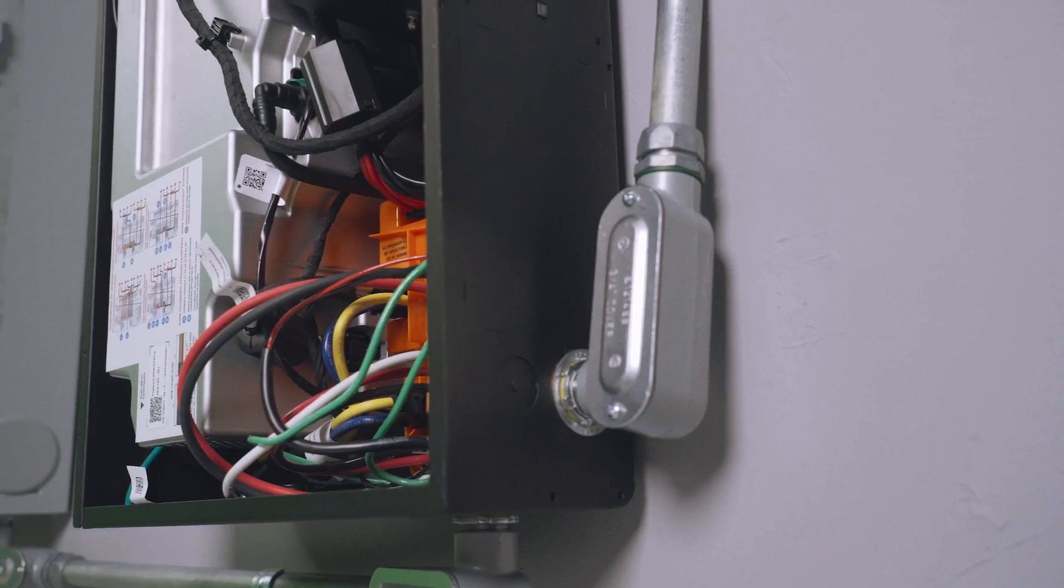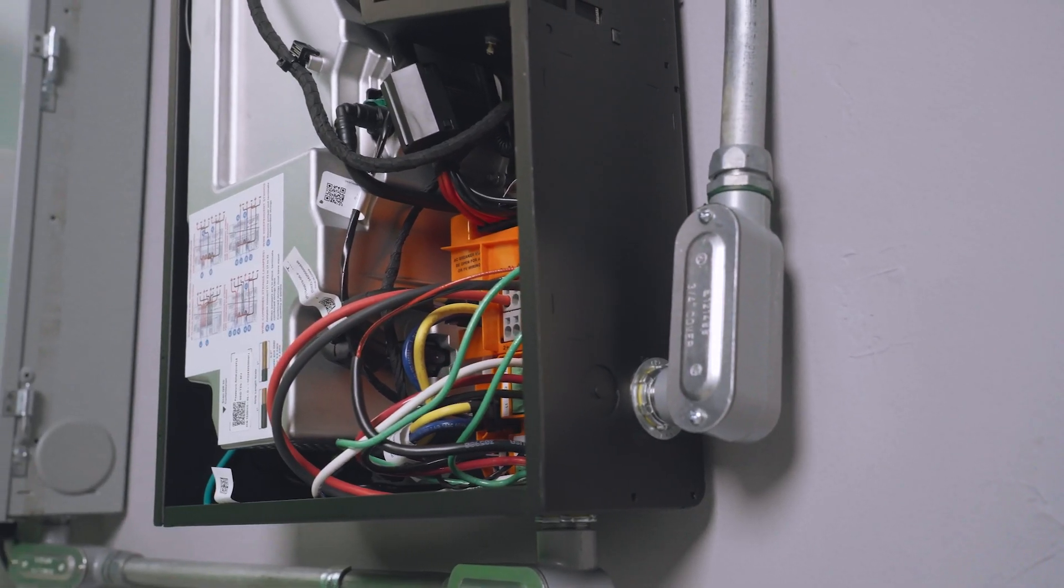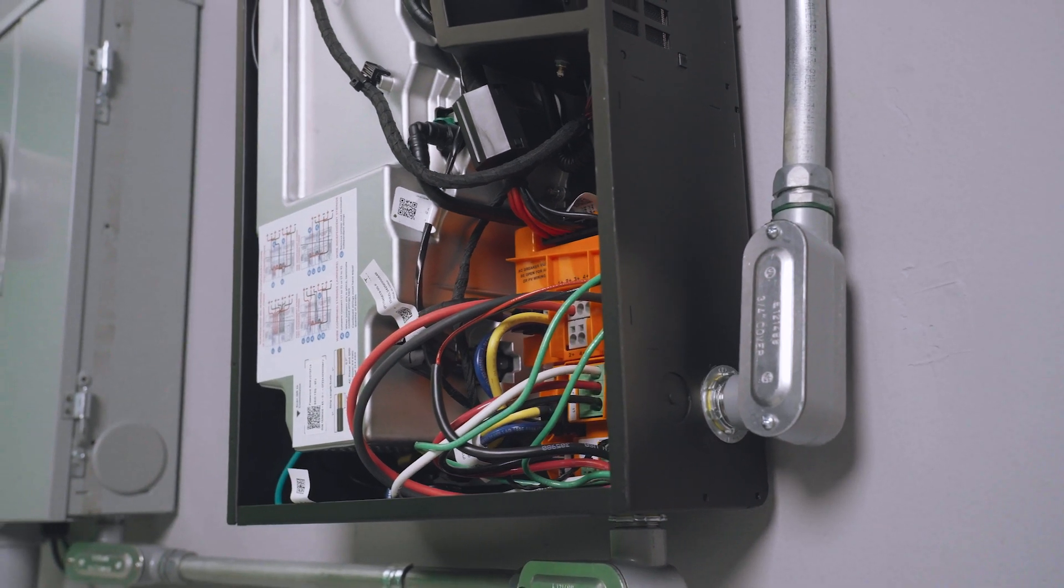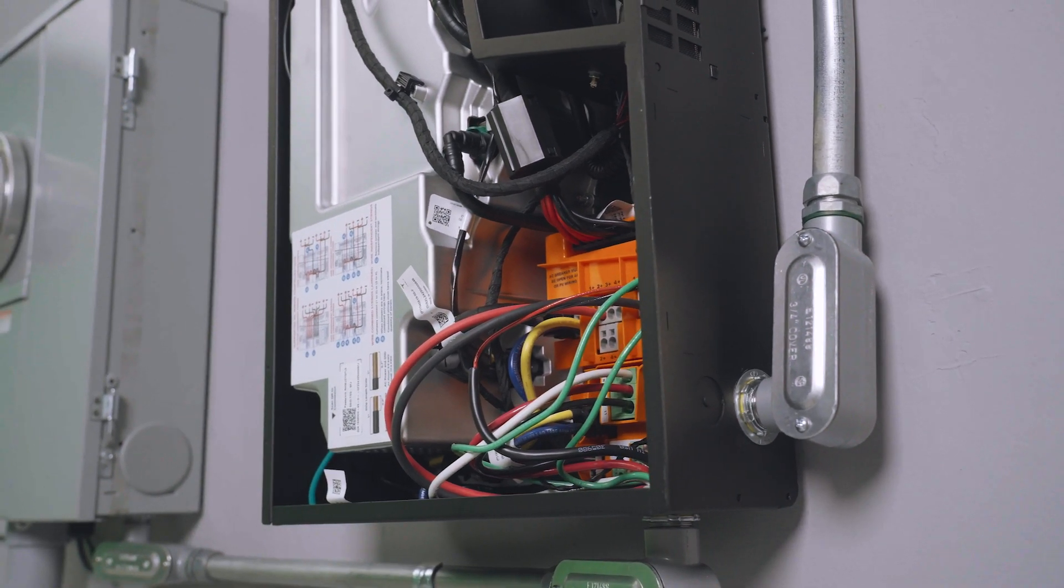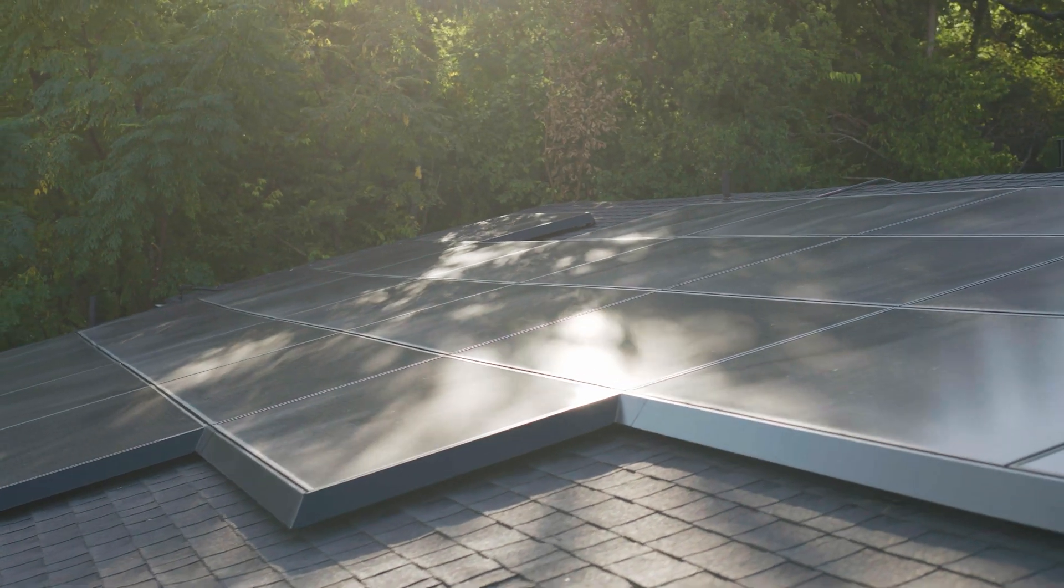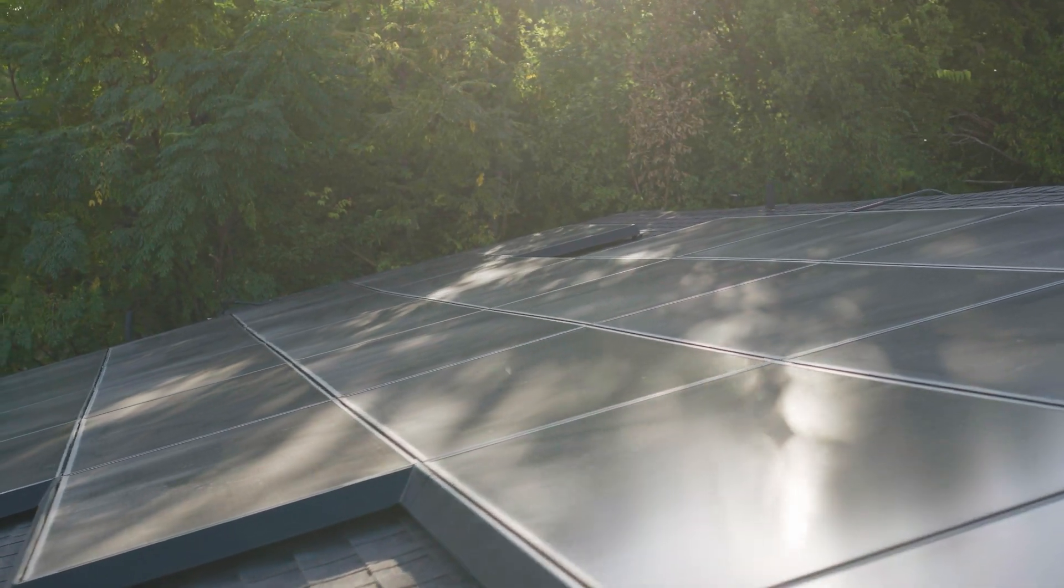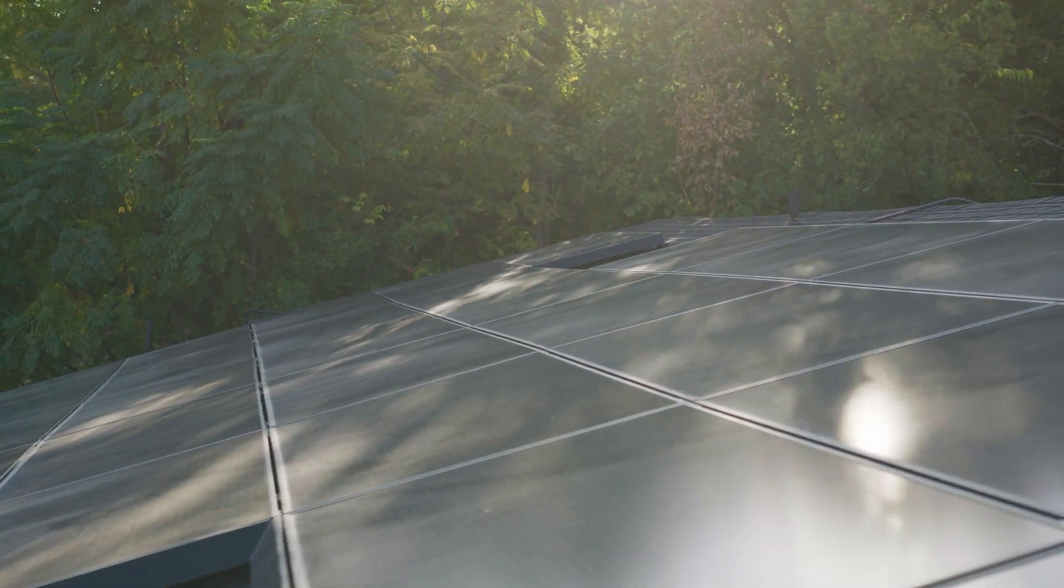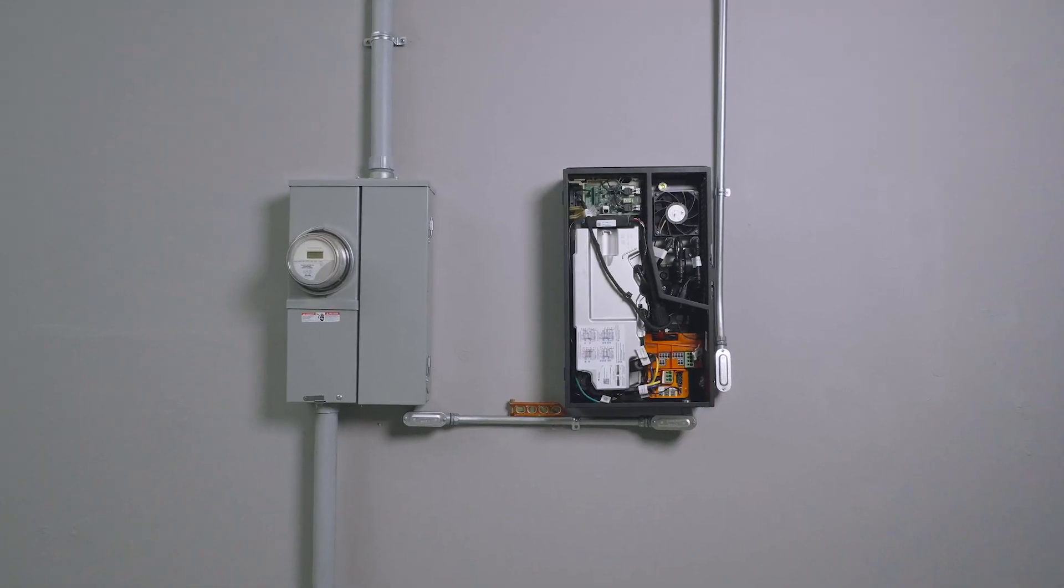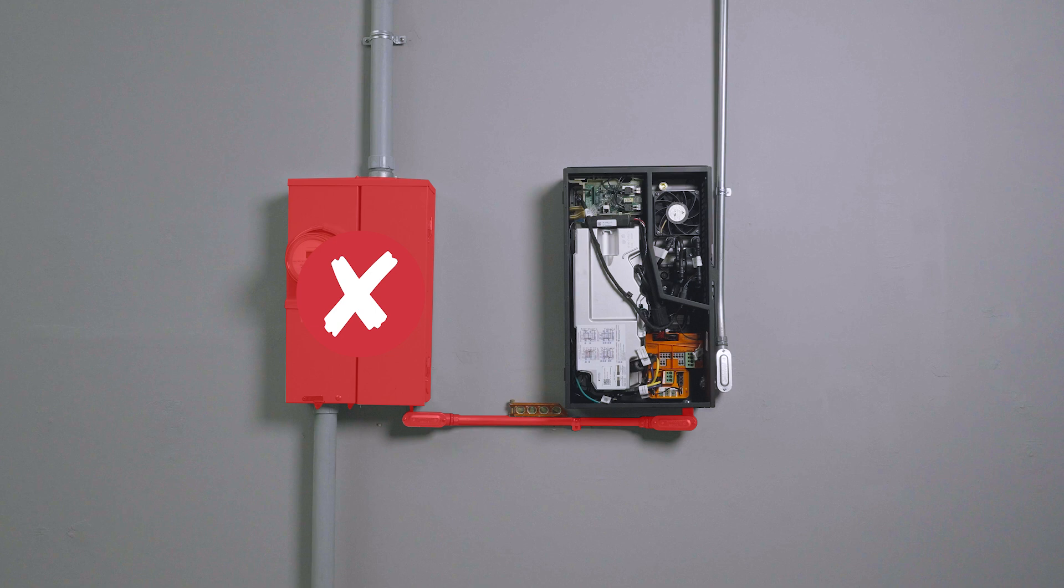To avoid the risk of electrical shock or damage to equipment, DC wiring must be terminated at the inverter first, before connecting the other end to the solar modules. Additionally, the inverter must not be connected to AC power when making DC terminations.